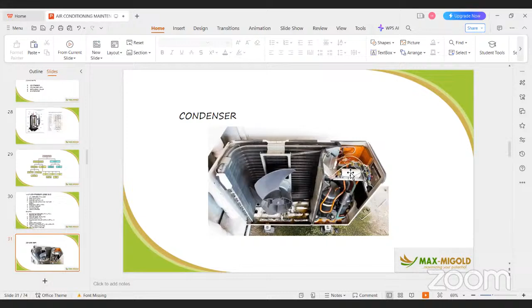But if you have a vendor that is maintaining your facility, call them to come in. They will come and give you what is needed. A common problem is a blocked condenser coil. If you put your condenser in a dusty environment, it will suck up the dust until it blocks itself. That blockage looks like a plank. Nothing can go through it.